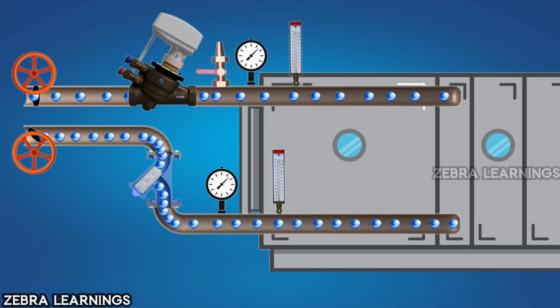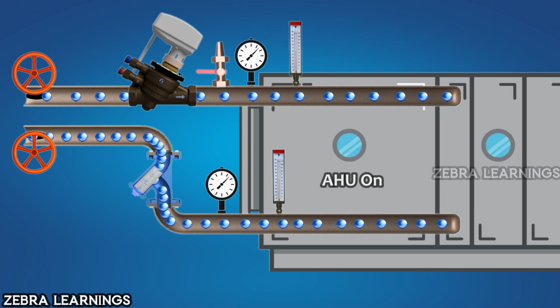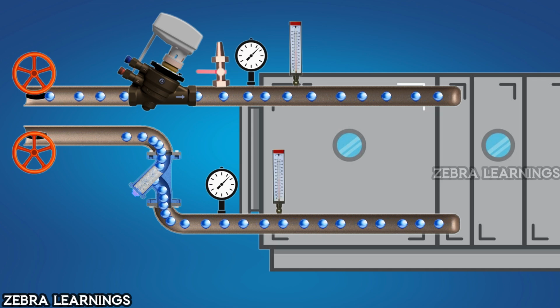If there is no air vent on the pipeline, we can remove the pressure gauge and release the air through that opening. After removing all the air, fully open the valve on the supply line and then fully open the valve on the return line. Now, the water will start flowing normally in the pipeline. So, this is the procedure to clean the strainer in an AHU pipeline.